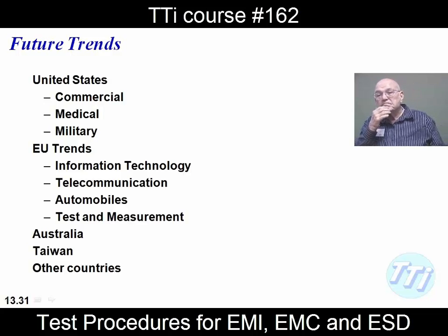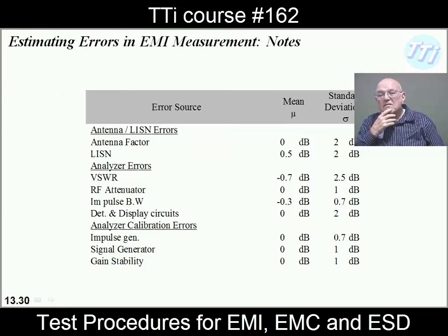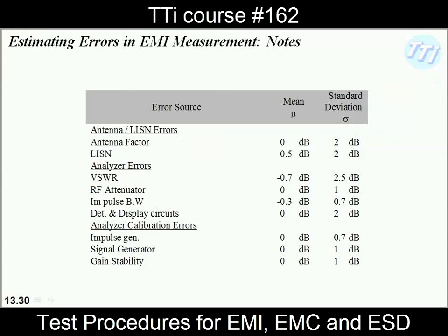Yes. So, will a spec sheet tell us about these errors? Will it be put in words of accuracy, or how will it tell us that? Sometimes accuracy, sometimes uncertainty. So what happens is that when the engineer is setting up the facility to test it, then you should be able to determine the actual accuracy and/or uncertainty with respect to that.